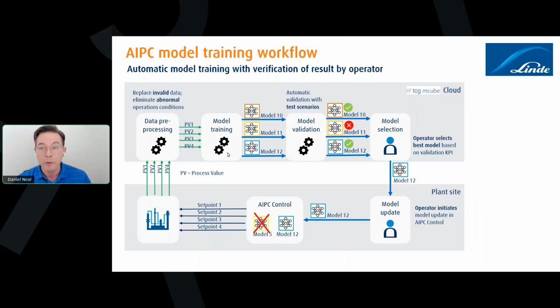You remove that data from the model and then you use the operational data that's at steady state to develop your new models. And so when you do model training, Linde has an automated model training technique where it validates these different models based on predefined test scenarios.